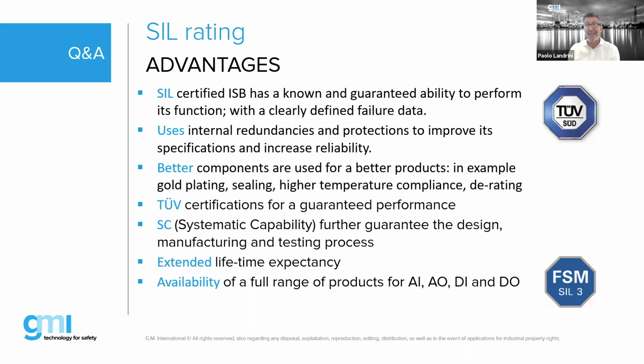To reach a SIL 3 level, you have to use better components than a standard product, so in the end you get a better product. You also have certification that guarantees the performance, the manufacturing, the design—the entire process is controlled, which is called systematic capability. It's not only the component that's SIL certified, but also the company that designed that product. You have extended life expectancy, and there are lots of products available today for SIL.